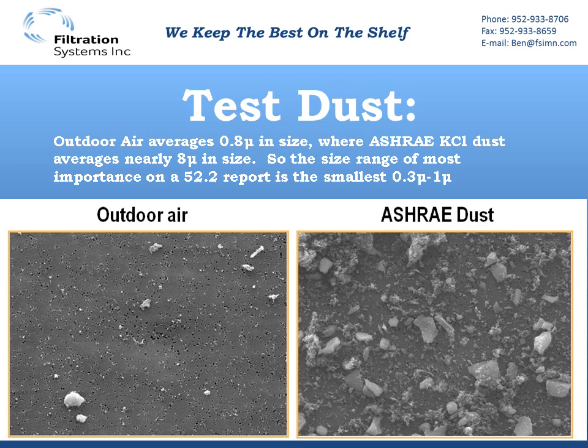This shows a picture of outdoor air and ASHRAE dust magnified. Outdoor air averages only about 0.8 microns in size, where the ASHRAE KCl dust averages nearly 8 microns in size. Most importantly in a 52.2 report, you should look at the smaller size range of 0.3 to 1 microns, as those are going to be the majority of particles actually in the air.